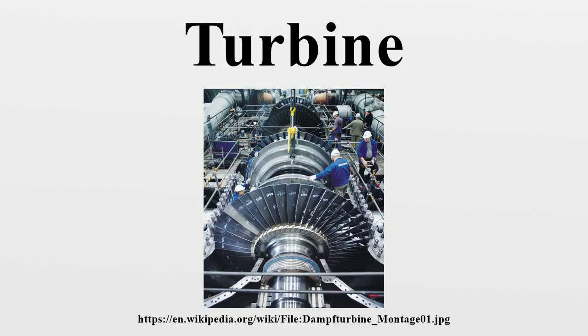Given the fluid flow conditions and the desired shaft output speed, the specific speed can be calculated and an appropriate turbine design selected. The specific speed, along with some fundamental formulas, can be used to reliably scale an existing design of known performance to a new size with corresponding performance. Off-design performance is normally displayed as a turbine map or characteristic.